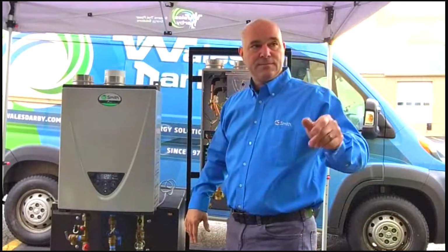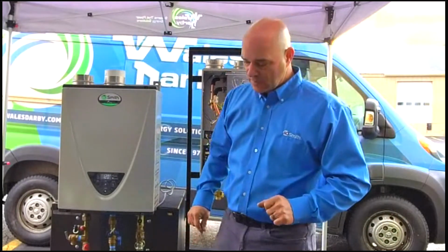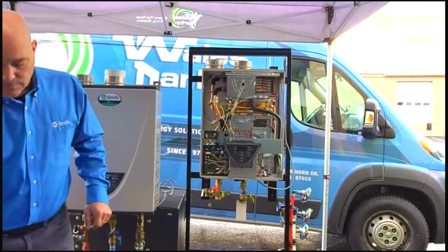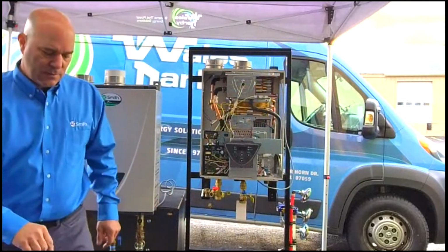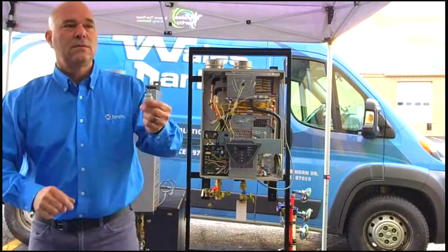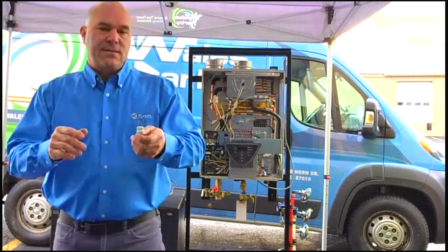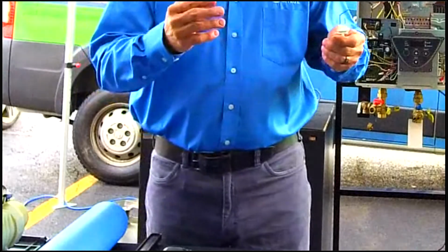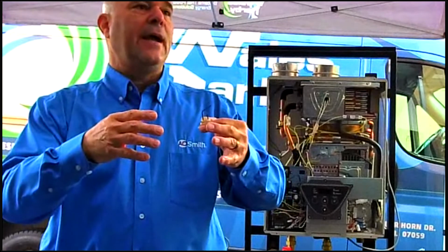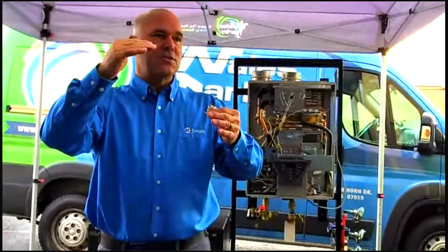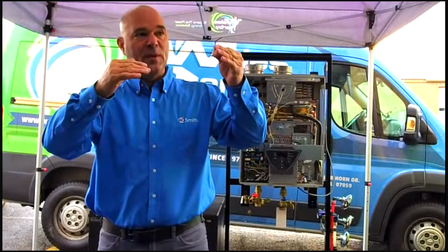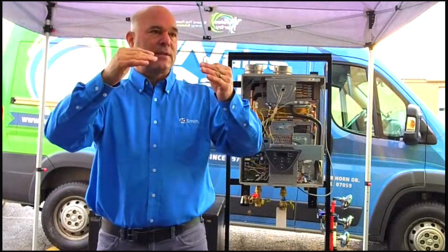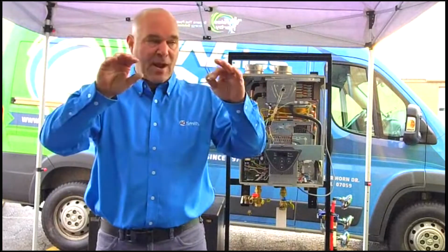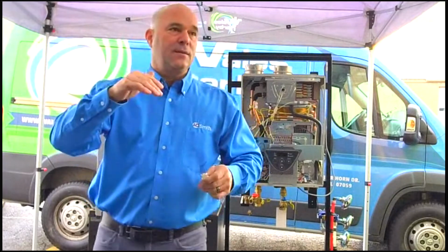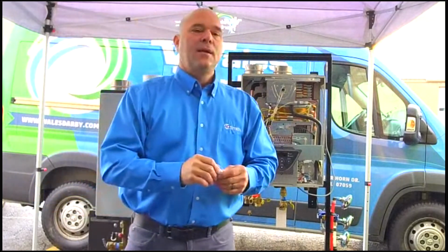Any questions on that? Not on that, but I do have one question, going back to the AFR. The question was, is that rod looking at ionization current? It's targeting temperature. So we're looking at combustion temperature, and we're either going to pulse the combustion blower or we're going to pulse open the gas valve to make sure that that target temperature is proper in the chamber so that it knows it's a clean flame.